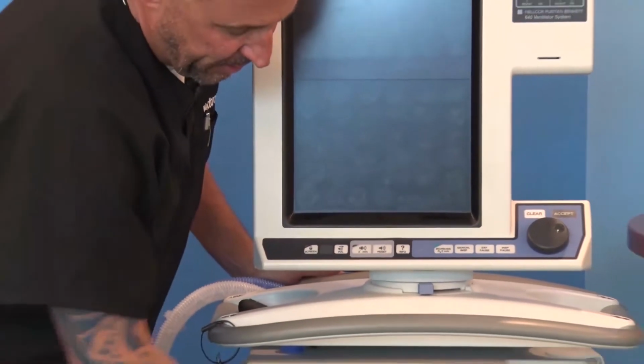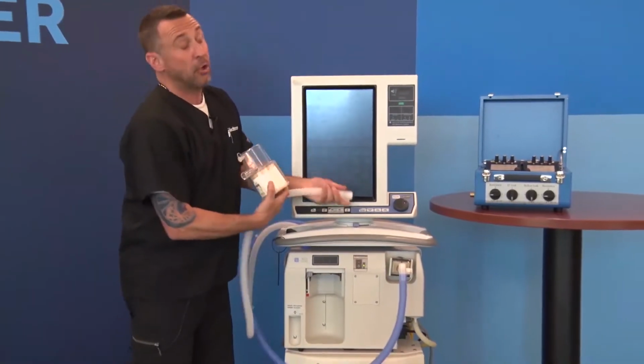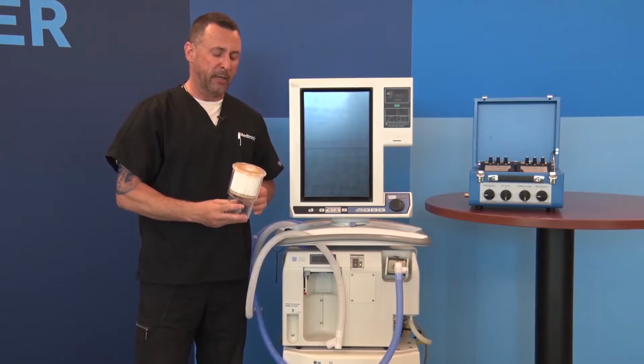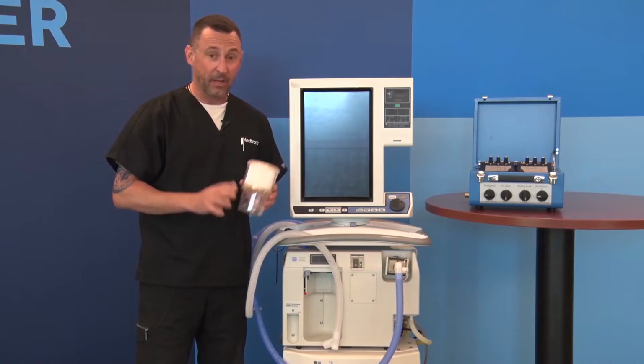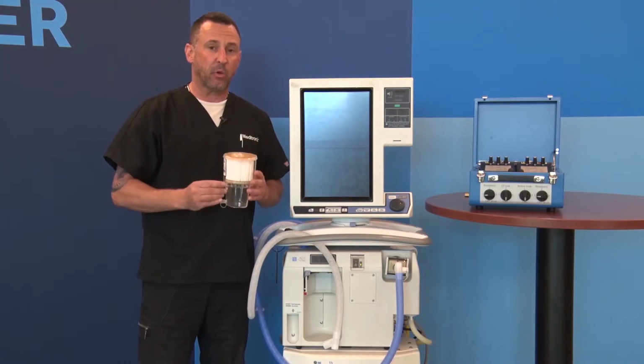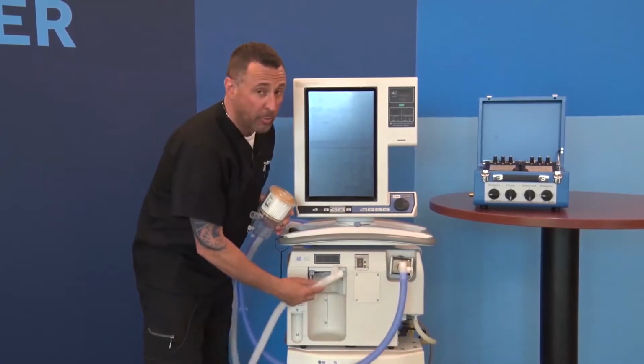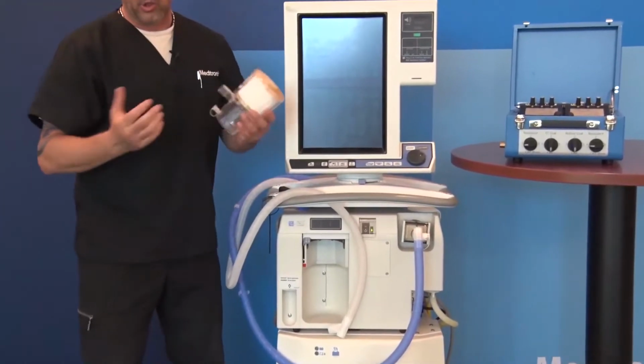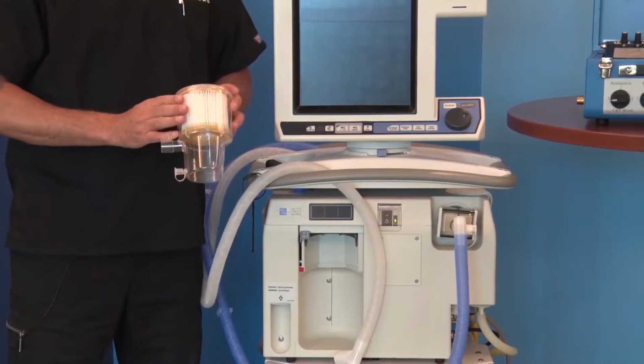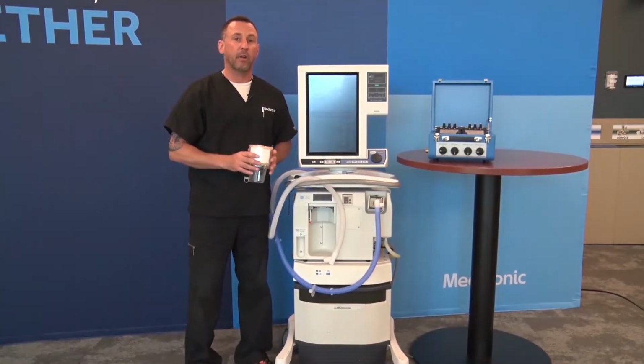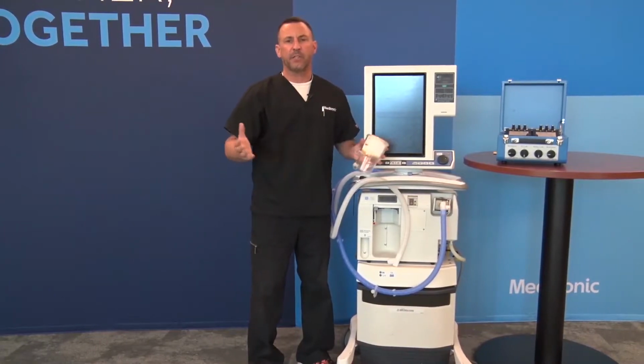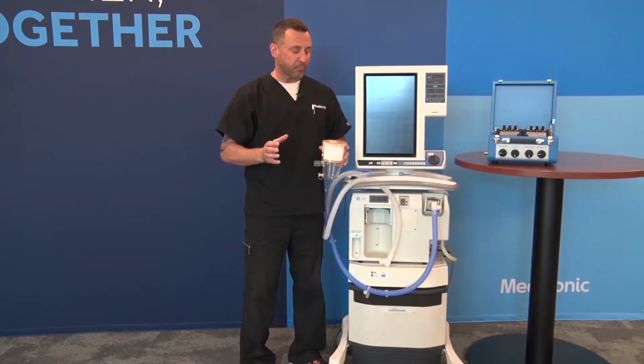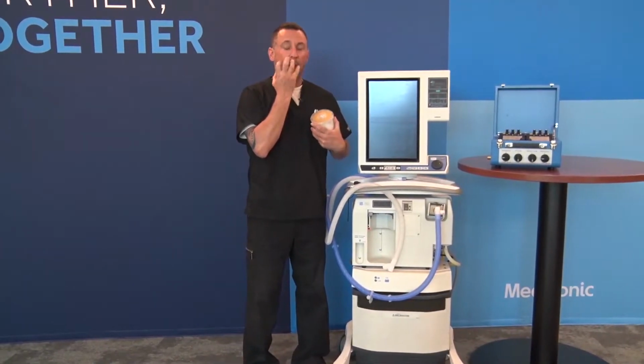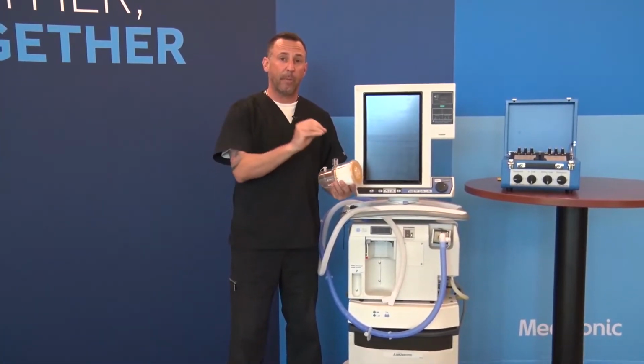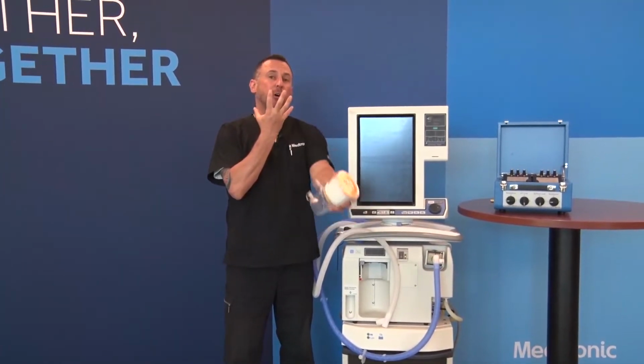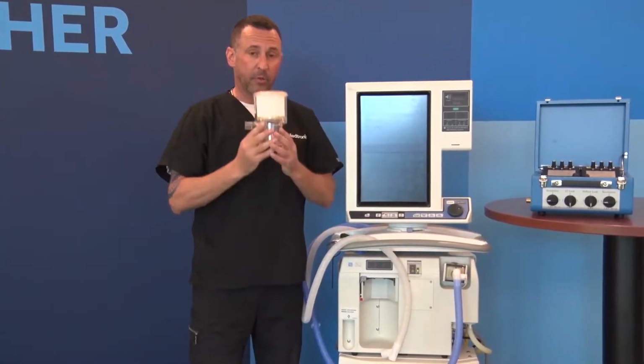The ventilator has an excellent filtration system. We utilize a NIOSH N100 efficiency rating heated integrated expiratory filtration system. That was a mouthful. What I'm telling you is the expiratory filter has to be used with this ventilator, meaning integrated. There's nowhere to put the tubing if you don't have a filter, so you have to use it. And I think you'll want to use it when you realize what N100 efficiency rating means. So N95 efficiency rating is kind of a standard in mechanical ventilation, as well as the filters, the masks we wear for, say, isolation rooms and such. N95 efficiency rating means for every 10,000 pathogens that hit that mask you're wearing, at the most penetrating particle size, which has been established as 0.3 microns, N95 will allow 500 of those 10,000 pathogens to pass through that medium. Our filter is an N100 rated filter.